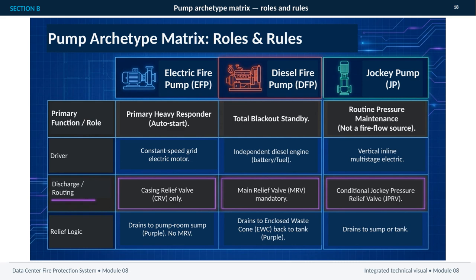The diesel fire pump, or DFP, provides total blackout standby. It is driven independently by a diesel engine with its own battery and fuel systems. Because of that role and configuration, a main relief valve is mandatory. Its relief discharge routes to an enclosed waste cone, then returns to the tank. Finally, the jockey pump is not a fire flow source. Its job is routine pressure maintenance, using a vertical inline multistage electric pump.